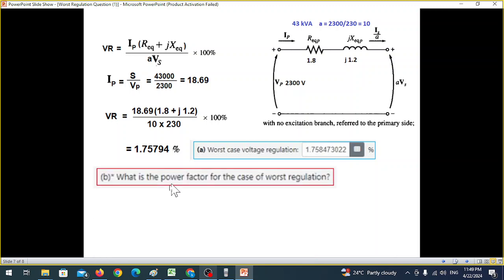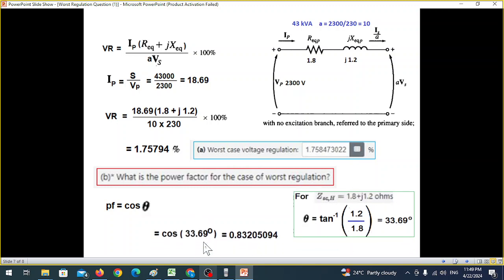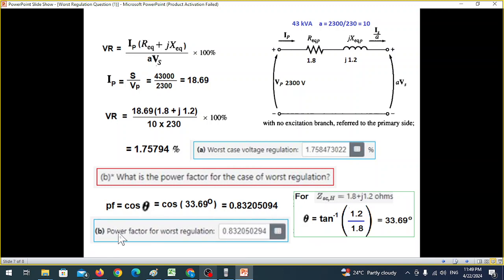Now coming to the second part: what is the power factor for the case of worst regulation? This was the value of VR, the worst case. Power factor is PF equals cos theta. We had calculated the angle to be 33.69 degrees. So we'll plug in that angle. And this is our answer for power factor. Here also we are very close to the answer given in the book, 0.832.